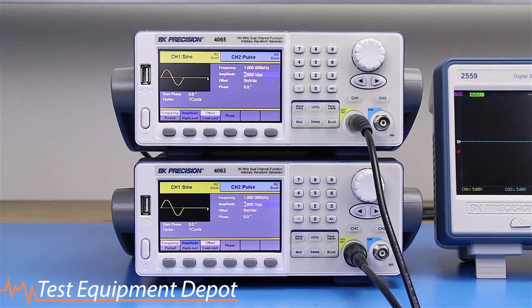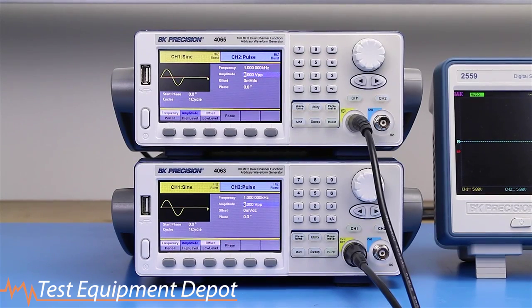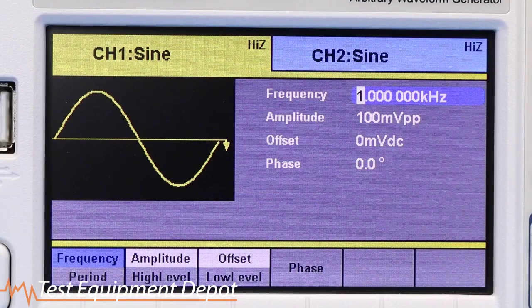First, set up your function generators to use a master timebase. This source could be from an external precision oscillator or distributed from one of the generator's own timebase. For this example, we will use one of the generators as the master timebase. On unit 1, set clock source to internal in the following menu.